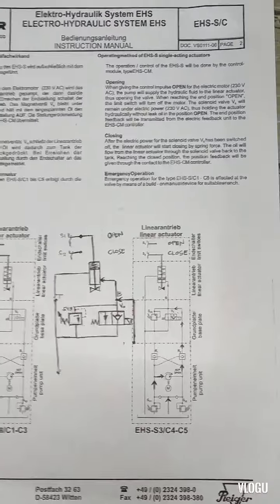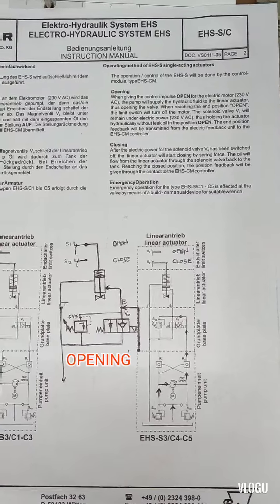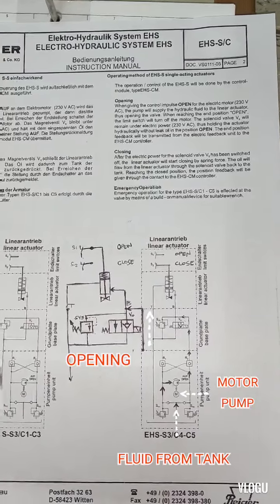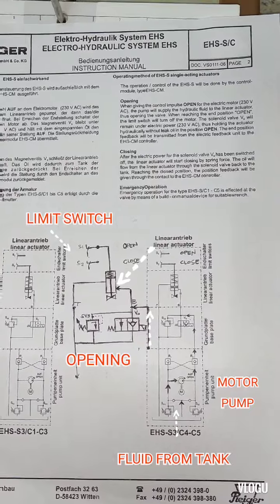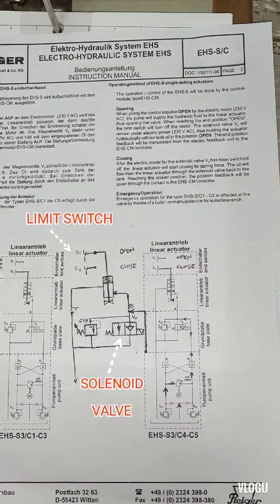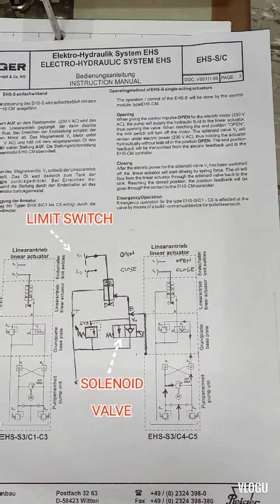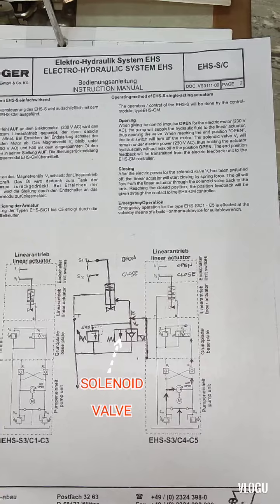Here is the hydraulic line diagram. For the opening sequence: when the control activates open, the electric motor at 230 volts AC drives the pump to supply hydraulic fluid to the linear actuator, opening the valve. When it reaches the end position, the limit switch turns off the motor. Solenoid valve V1 remains under electric power, holding the actuator hydraulically without oil leak in the open position. The end position feedback is transmitted to the CM controller.